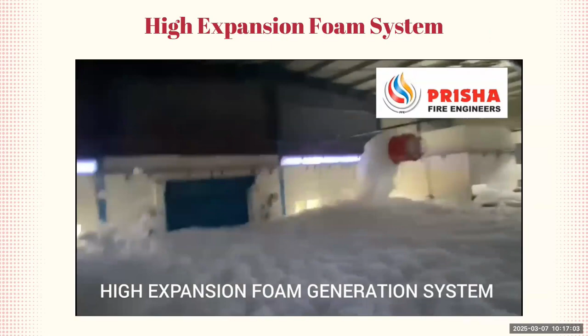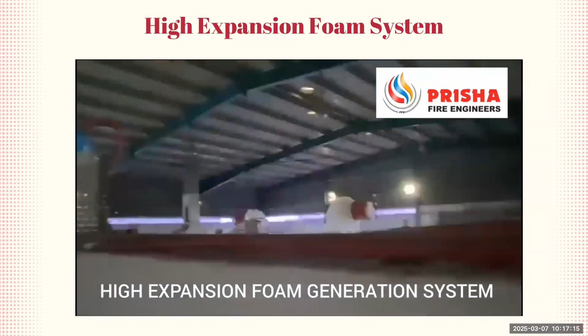Is this system better because it's a thicker foam? Compared to the sprinklers we just saw, yes for sure, but it depends on the area and type of fire you want to suppress. This one is strictly foam, while the other was a mixture of water and foam, because the foam helps cool and prevents the release of flammable vapors. So in certain applications, water alone is not enough.